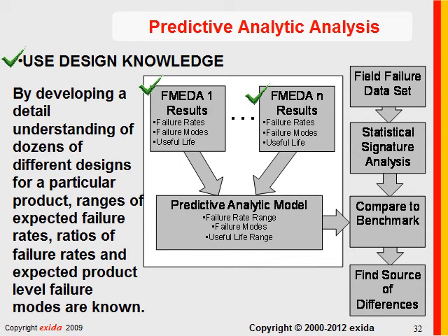But the Excellentia program takes care of that with the maintenance capability modeling. So in any case, I'd love to see more field failure data. I'd love to see end users eventually get real life failure rates. In the meantime, I think FMEDA data is 20 to 50% conservative, and that's an excellent source for purposes of the initial designs.